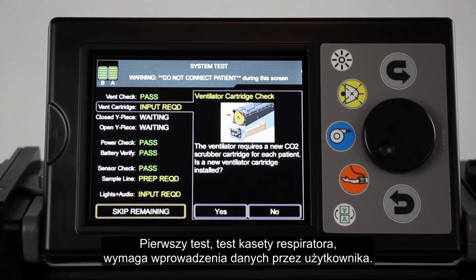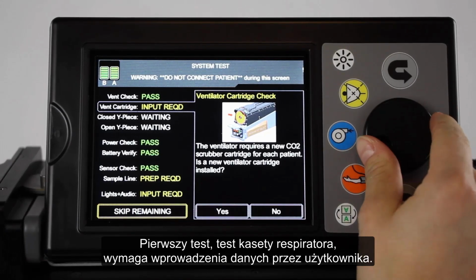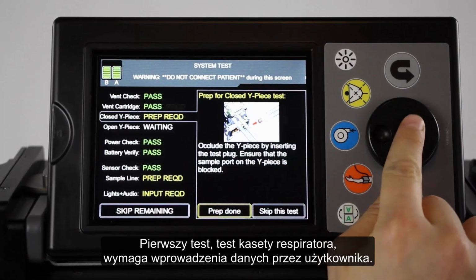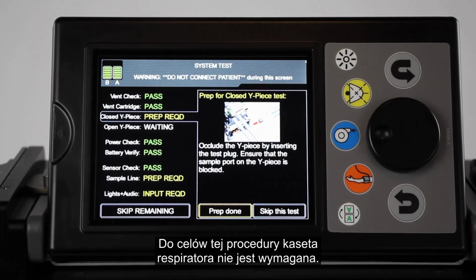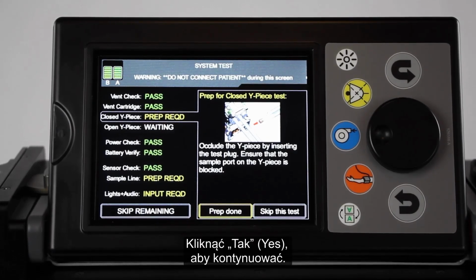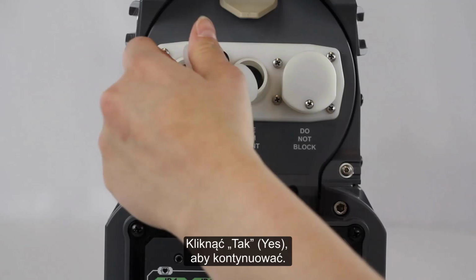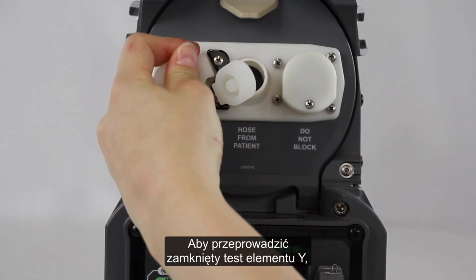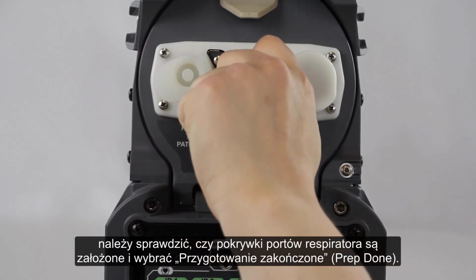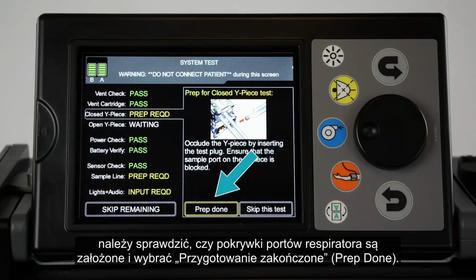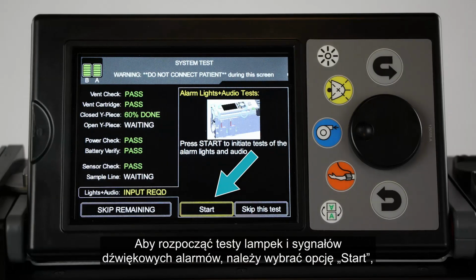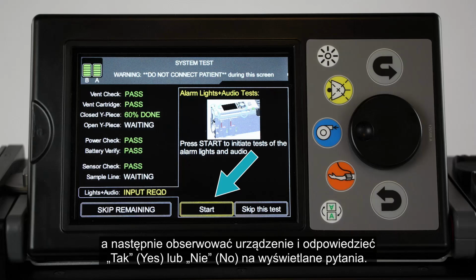The first test, Ventilator Cartridge Check Test, requires user input. For the purposes of this procedure, a ventilator cartridge is not required. Select Yes to continue. To complete the closed Y-piece test, simply ensure that the ventilator port covers are installed, then select Prep Done. To initiate the alarm lights plus audio tests, select Start, then observe the device in order to answer yes or no to the displayed questions.